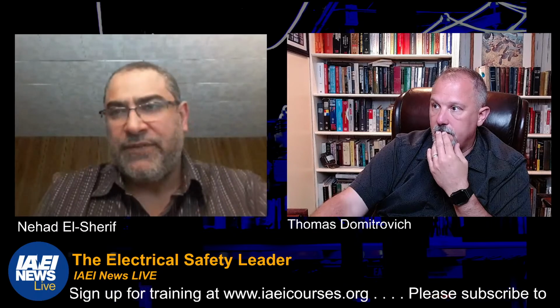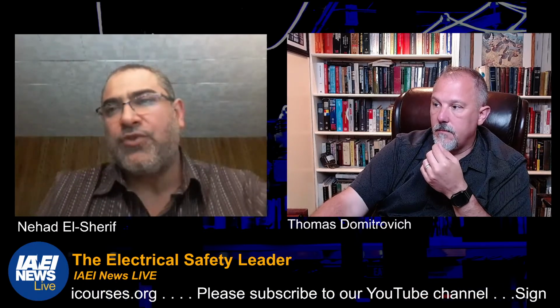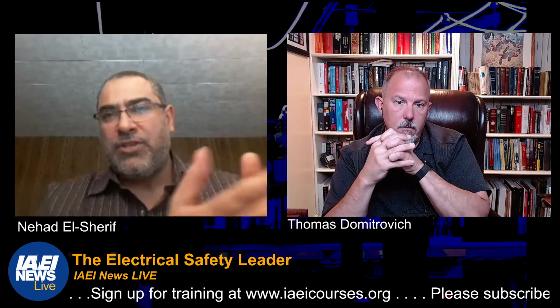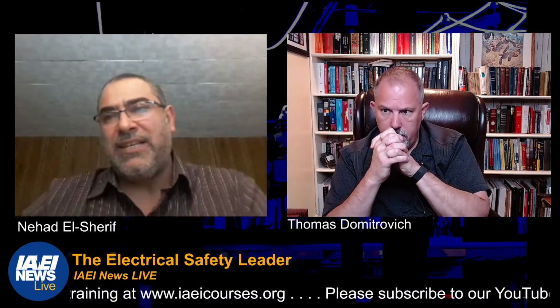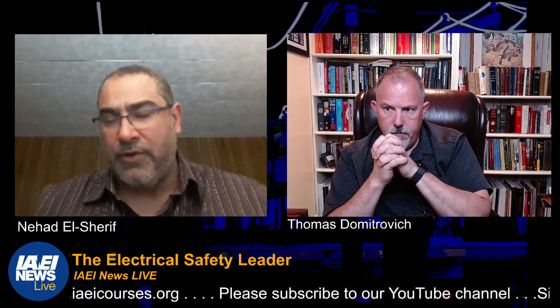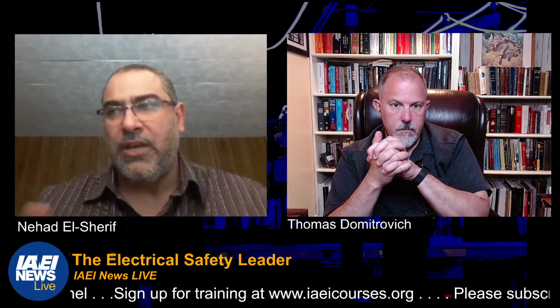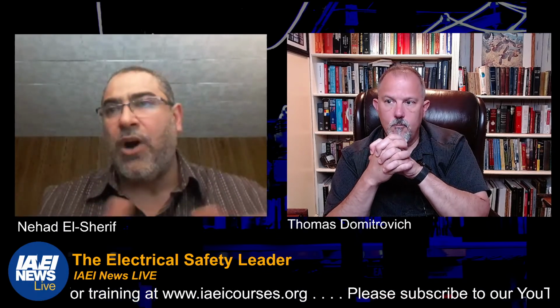Just remember, you are not trying to replace Class A with special purpose GFCIs. Class A is your go-to until you get to an application where you can't use Class A. Then you start considering Class C, D, and E. What Tom and I would like to emphasize is that those new classes are not to replace Class A. They're not better. It's just a complement. Now we have a family of classes. Use Class A, and in those cases where you couldn't use Class A, because, let's say, the voltage was higher than the commercially available Class A products, or the leakage current in your system was just too high, you consider the others. You can install a Class A and it keeps tripping all the time because the inherent leakage current, the charging capacitance, is too high in your system.